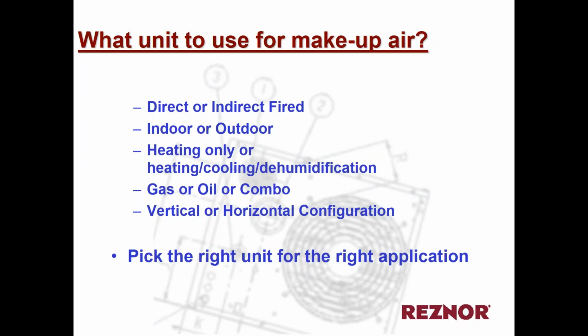So we make a plethora of units that can be used for make-up air. Indirect fired, we talked about, units that have a heat exchanger that separates the combustion side of the burner from the air distribution side. And we also make direct fired burners, which is a burner that fires directly into the airstream. These can be in an indoor or an outdoor configuration. They can also be heating only, or they can provide cooling and dehumidification for areas where that's required. They can be gas-fired, either natural or propane gas, or they can be oil-fired. We make large oil-fired units, or a combination of both. It can be in a vertical or horizontal configuration. So this is where John or Wayne or Brian would come in and be able to help you pick the right unit for the right application.